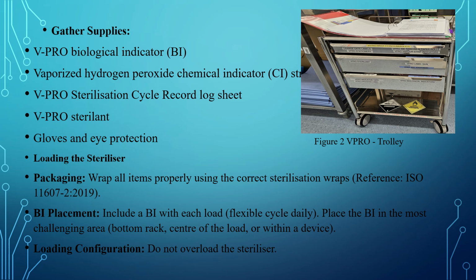The reason for not overloading the machine is that if you overload it, the vapor won't penetrate into the RMDs, which won't allow the hydrogen peroxide to penetrate to and from the RMDs.